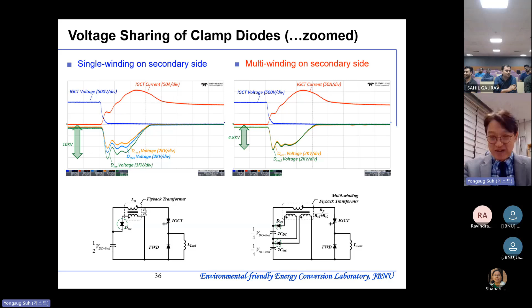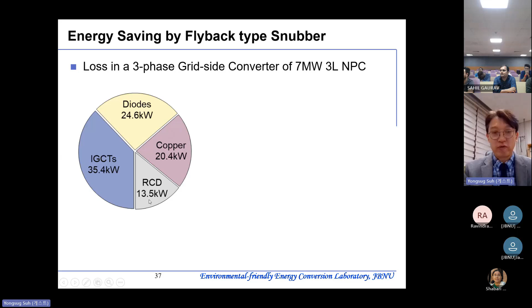Energy saving by the flyback type snubber is the major goal. We compared the loss breakdown for a 7 megawatt 3-level NPC case. The diode consumes 24.6 kilowatts, and the IGCTs 35.4 kilowatts. Copper refers to the copper loss of the flyback type snubber inductor, and RCD loss is 13.5 kilowatts. If we use the flyback type snubber, the whole RCD loss is gone.